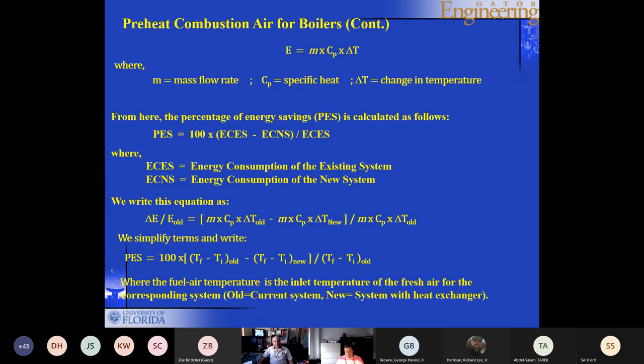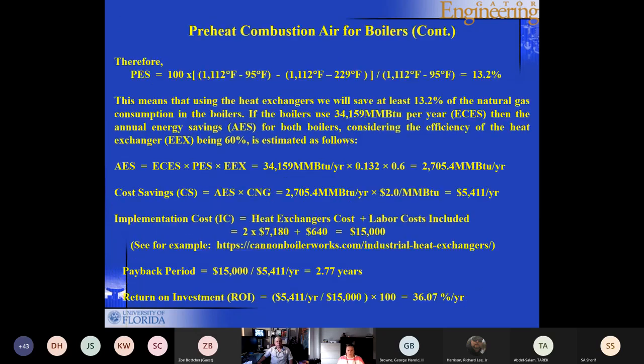And if you translate that into symbolic form, you get the equation that delta E over E old equals whatever it is here. I don't want to spend my time reading it for you. We simplify the terms, and you end up with the percentage energy savings, because the m and the Cp are the same in the numerator and the denominator, so they cancel out. You end up with T final minus T initial old, minus T final minus T initial new, divided by T final minus T initial old. That is where the fuel air temperature is the inlet temperature of the fresh air, and the old is the current system and the new is the system with the heat exchanger. And therefore, when you plug in the numbers, you get 13.2% energy savings. This means that using the heat exchanger, we can save about 13.2% of the natural gas consumption in the boilers.